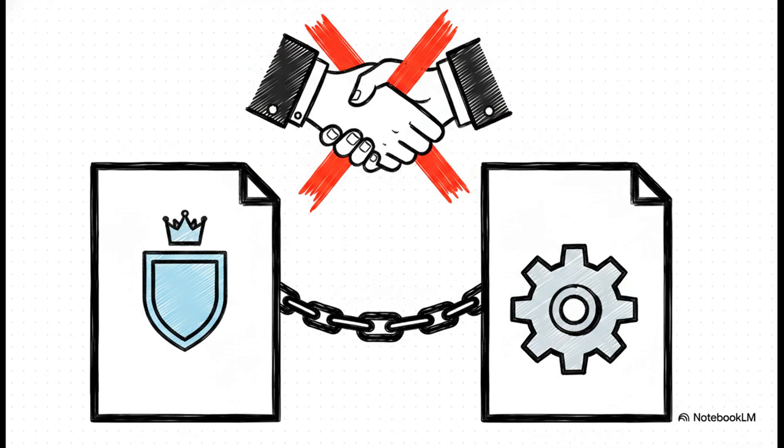Now, to manage this critical relationship, handshakes and informal emails are completely useless. You need two robust, living documents. First, a quality agreement. This legally defines roles, responsibilities, mandatory change notifications, and your rights to actually audit their facility. Second, a technical agreement. This one explicitly lists the validated process parameters, calibration standards, and exactly what data must be included in that batch release package. Together, these two documents are what make your expectations genuinely auditable.